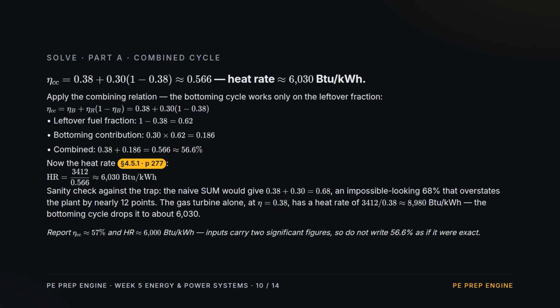Apply the combining relation. The leftover fuel fraction is 1 minus 0.38, which is 0.62. The bottoming cycle contributes 0.30 times 0.62, which is 0.186. Add the topping efficiency back. 0.38 plus 0.186 is 0.566, about 57%. Invert for heat rate. 3412 over 0.566 is roughly 6,000 BTU per kilowatt hour.